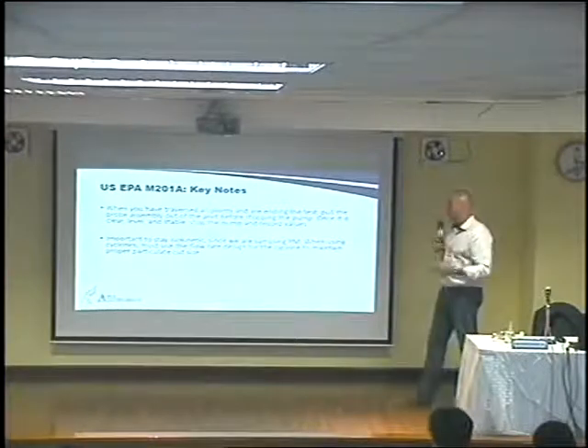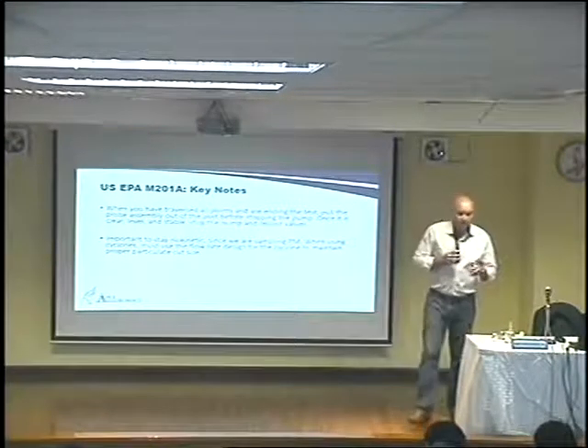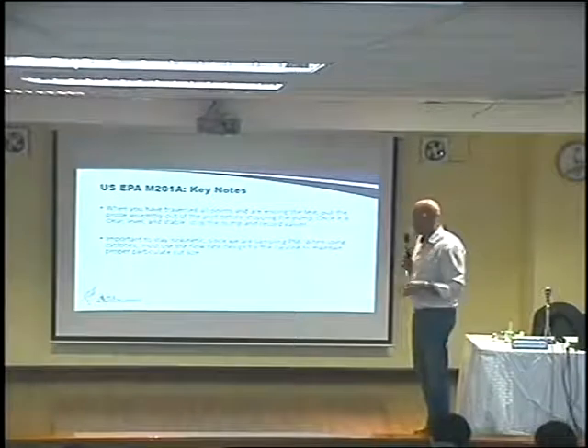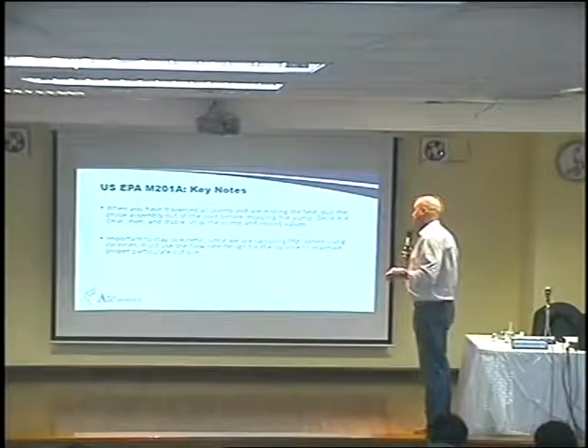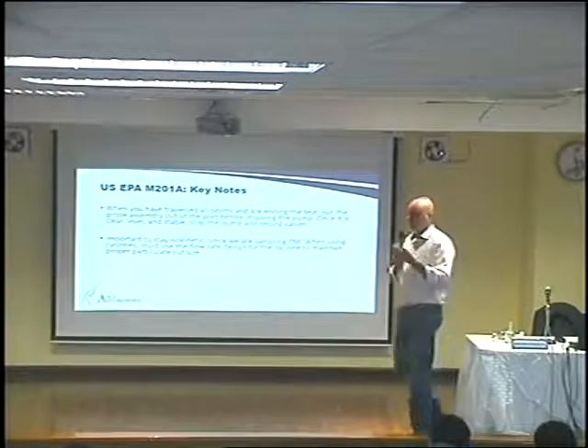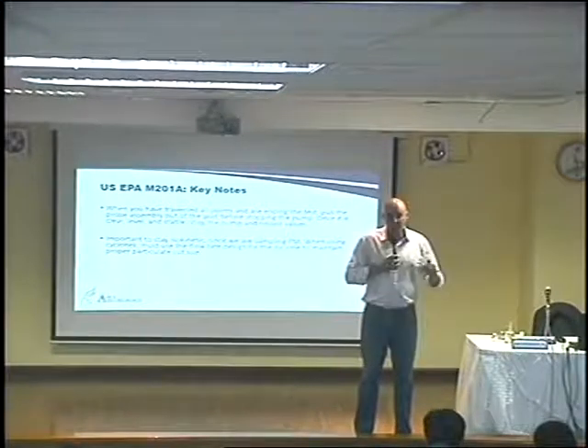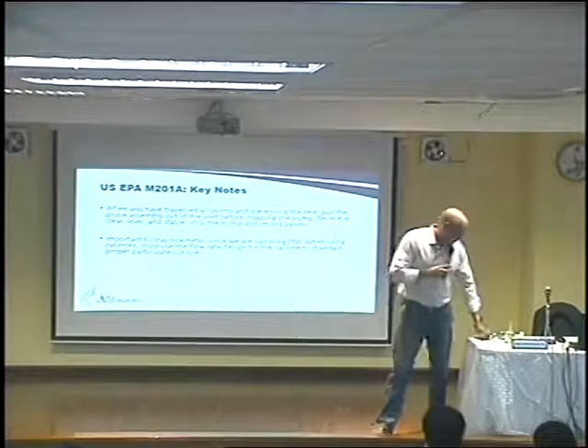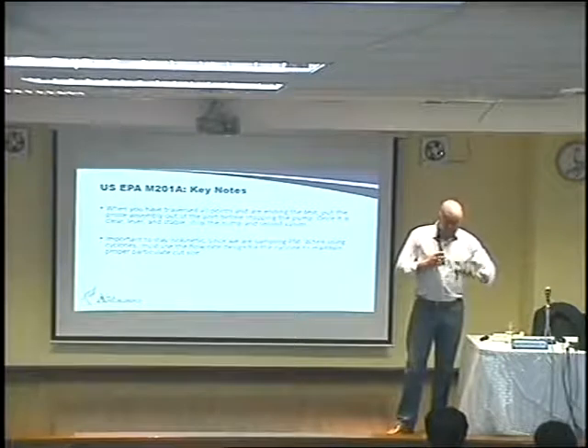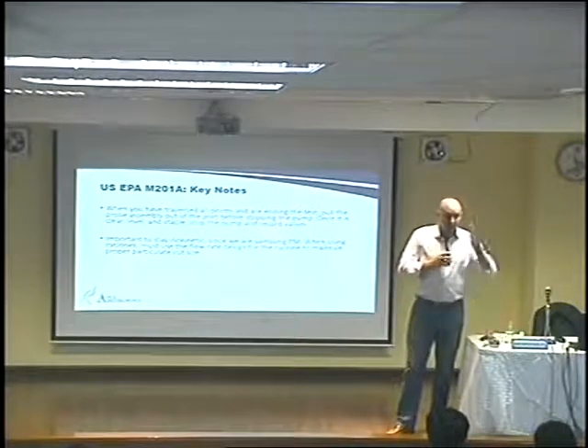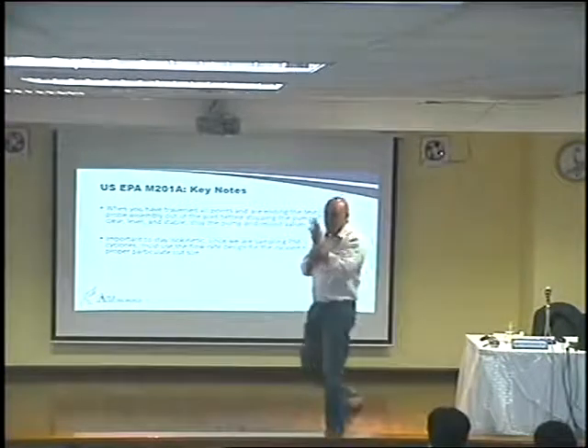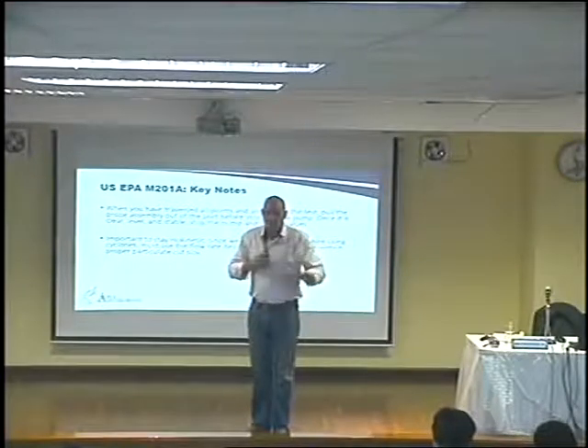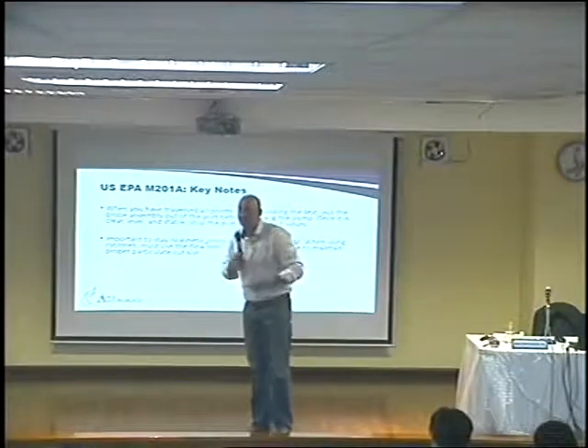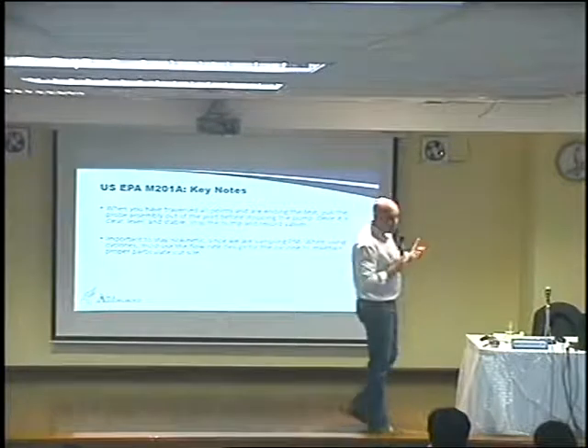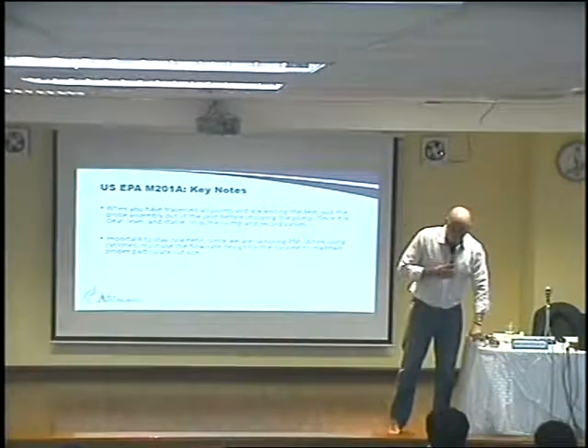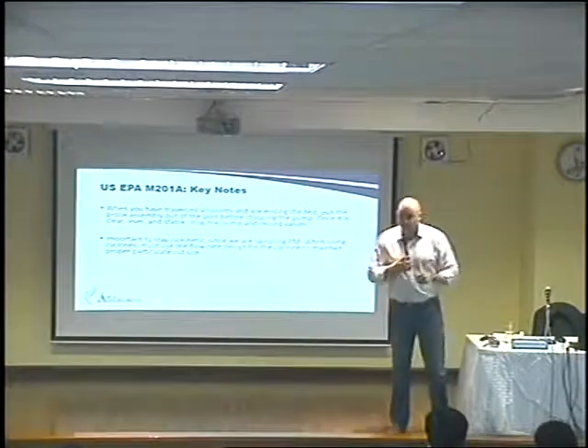So the flow rate's a little bit different, as we talked about. Again, we won't go into a lot of detail in the calculations, but it's important to maintain the flow rate through the nozzle to make sure that the cyclone here is cutting the size of the particulate in the correct manner as it flows around the cyclone. And that's, again, all based on the calculations that we'd have for determining our nozzle size and our flow rate and things like that.